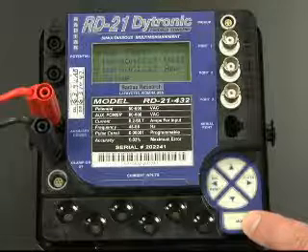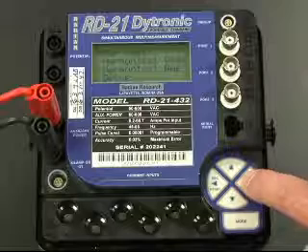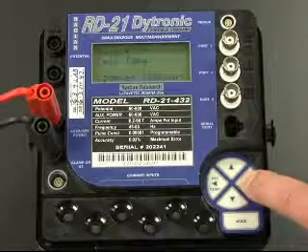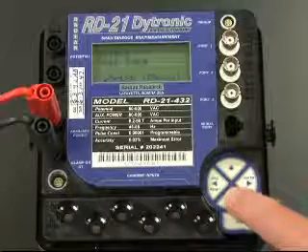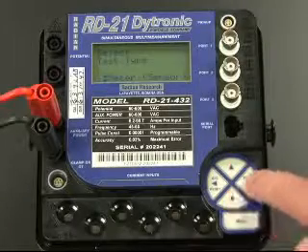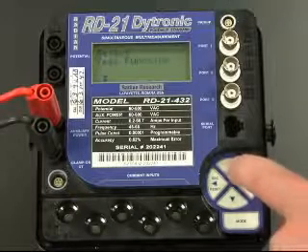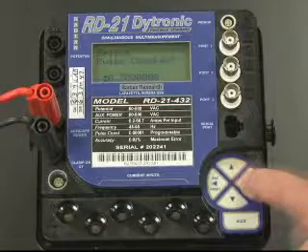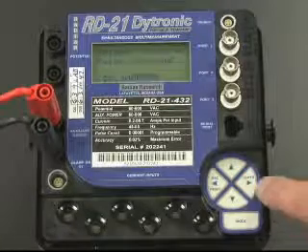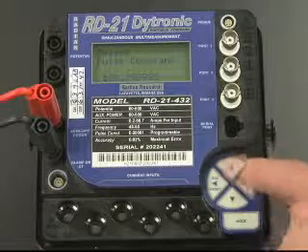Within the main menu, use the arrow buttons to move the cursor to the Run Test option. Press the Enter button. Press the up and down arrow buttons until the meter Sensors option is reached and press the Enter button. Scroll through the test functions supported by the standard and press the Enter button when the correct function is displayed. Use the keypad to select the correct K sub H for the meter and press the Enter button.